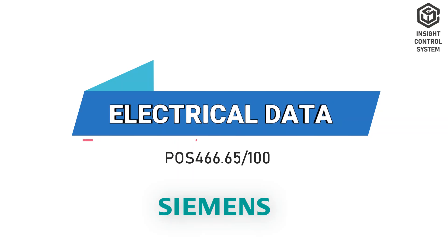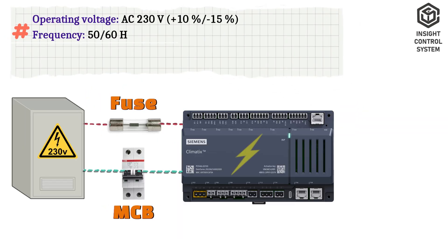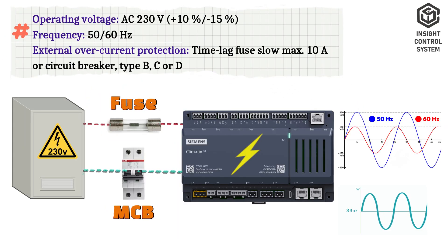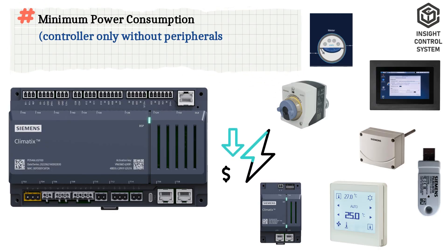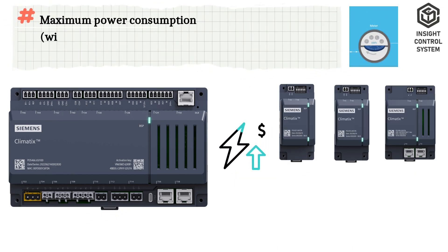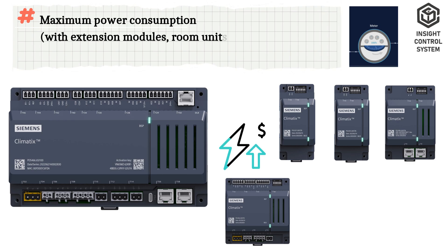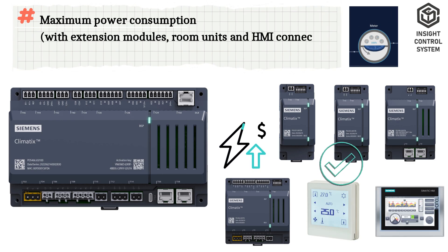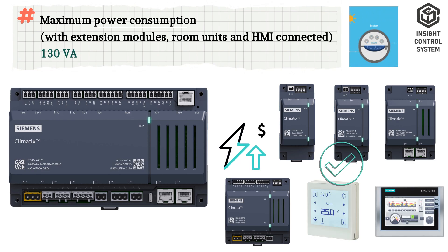Electrical data: Operating voltage is AC 230 volt, frequency is 50 or 60 Hz. Minimum power consumption is 4.5 watts (controller only, without peripherals connected). Maximum power consumption is 130 VA, with extension modules, room units, and HMI connected.